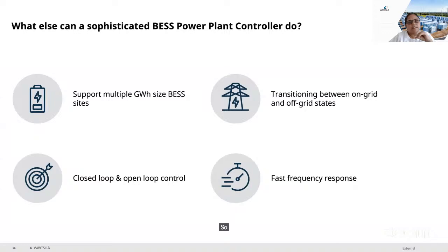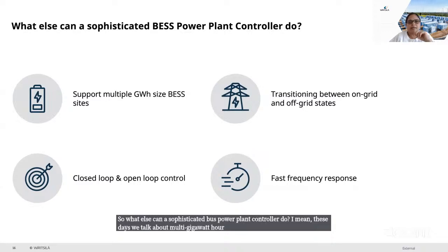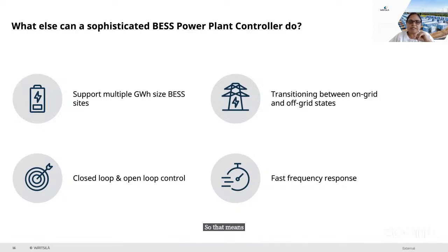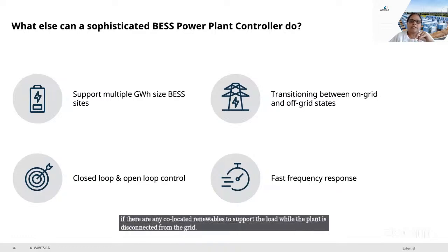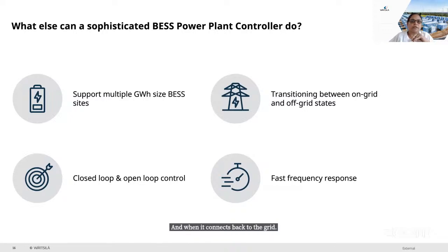So what else can a sophisticated BESS power plant controller do? These days we talk about multi-gigawatt hour size BESS sites, not 100 megawatt anymore, not 200 megawatt anymore, but multi-gigawatt. That means the BESS PPC needs to scale to support these multi-gigawatt hour size sites. And also some utility customers like their site or plant to be islanded when the grid connection is lost, of course utilizing grid-forming capable inverters, and if there are any co-located renewables, to support the load while the plant is disconnected from the grid. And when it connects back to the grid, they want the site or plant to go back into on-grid mode.